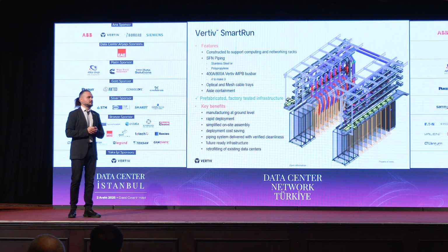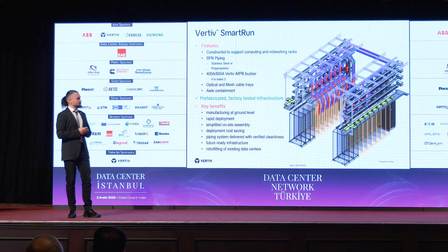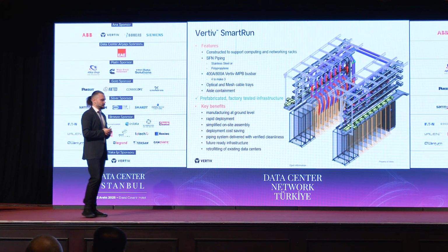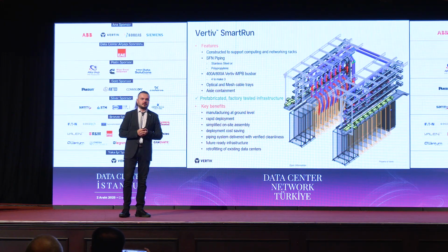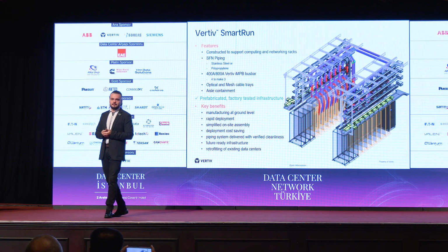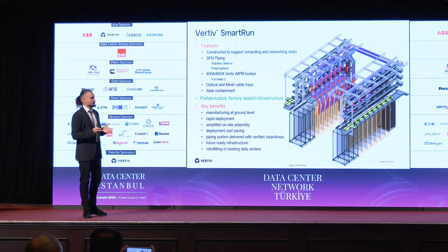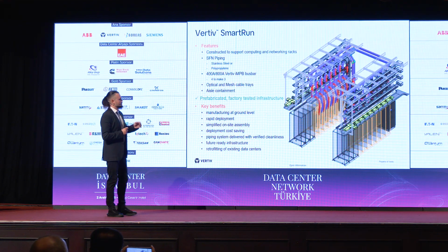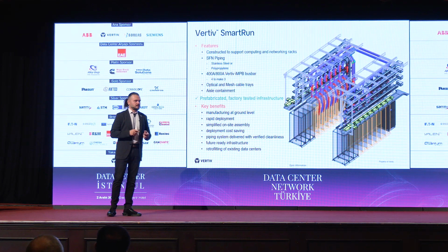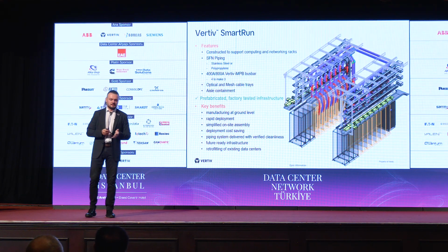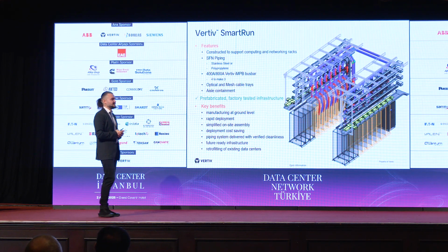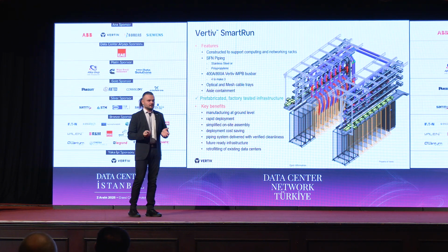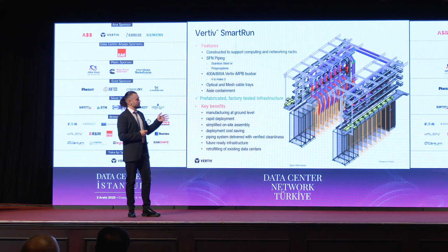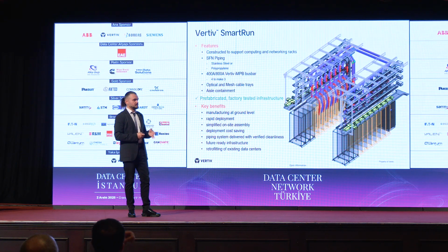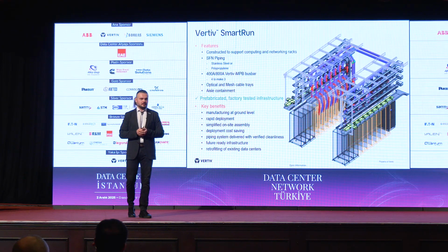We're calling this SmartRun. SmartRun was developed specifically for the NVIDIA equipment. We started from GB200. It's an overhead structure, which is quite massive. You see the height of the structure is more than 2 meters, basically more than the height of the rack itself. But there's a reason for it. We are accommodating the secondary fluid network. It's a steel piping. We are accommodating a 4 busbar system.